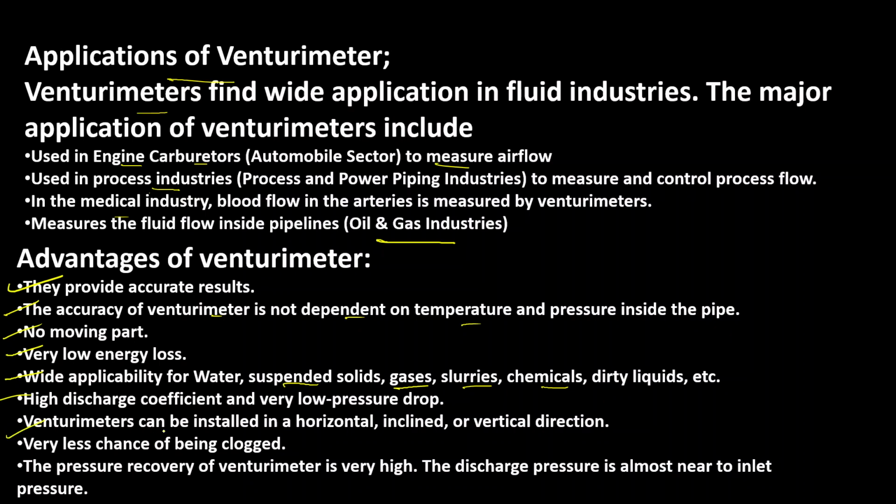Venturimeter can be installed in horizontal, inclined or vertical direction. It can be used in all directions. Very little chance of being clogged. This is also a very important point: the pressure recovery of venturimeter is very high. Discharge pressure is almost near to inlet pressure.